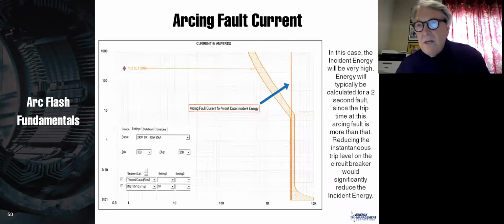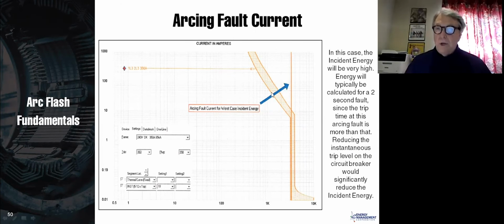Here's the second line. This is in the Schrodinger's cat area. So is it going to trip or not? I don't know. It looks like it may trip, but I can't guarantee it's going to trip because it's in that unknown area. And therefore, if this portion of that instantaneous is under the arcing fault, then how long could it take to trip? Well, let's go right here. We'll go up and over, and that looks to me like 7 or 8 seconds. So in an arc flash, that circuit breaker could take 7 to 8 seconds to trip. Therefore, our program is going to only calculate it for the first 2 seconds, and we're going to get a very high number of calories.